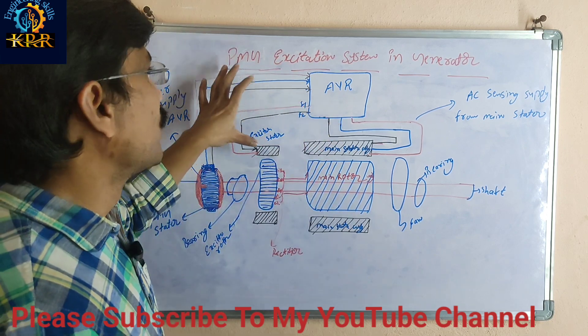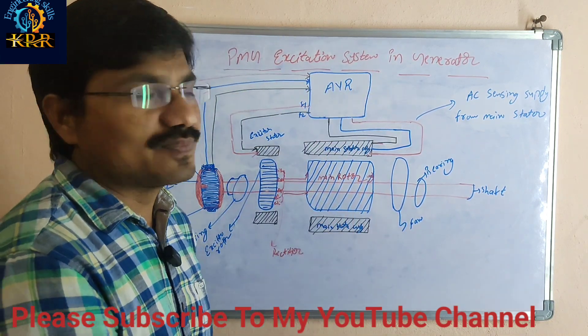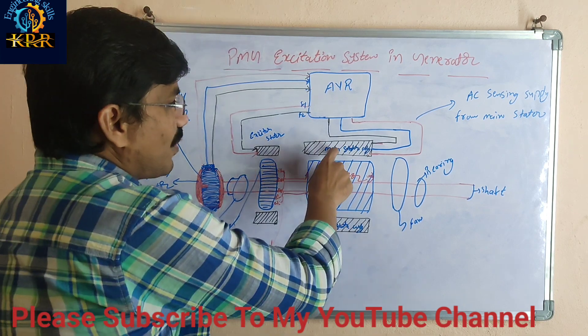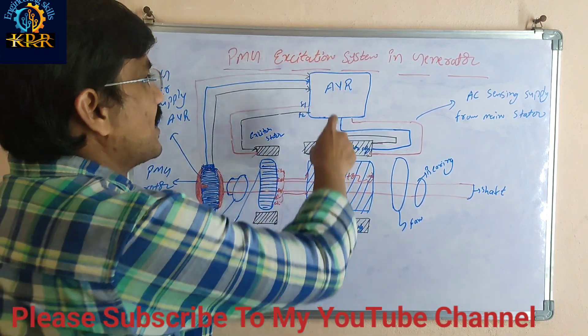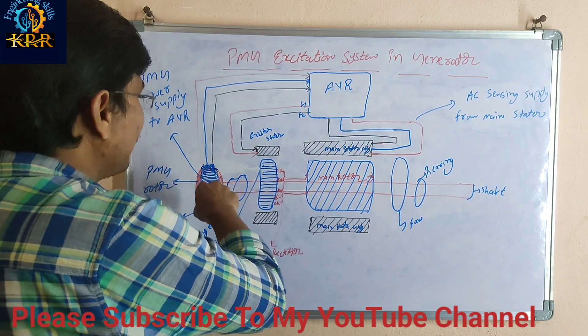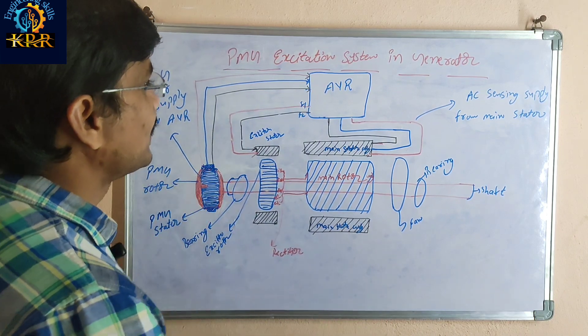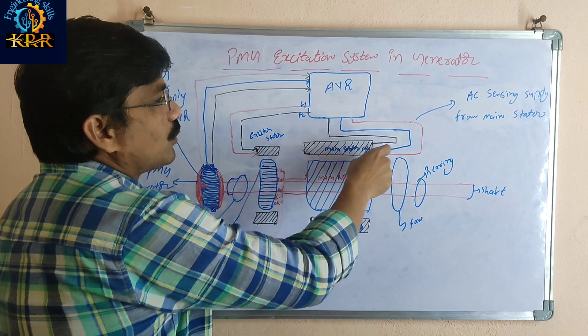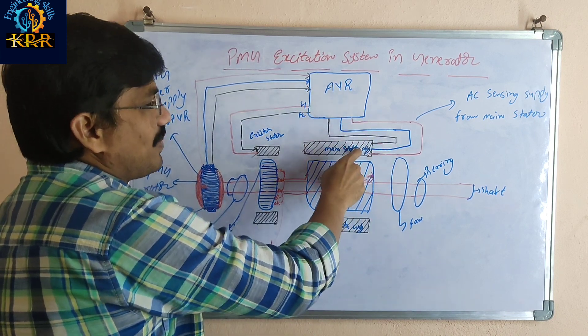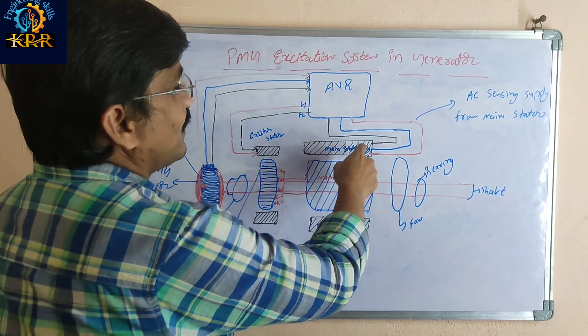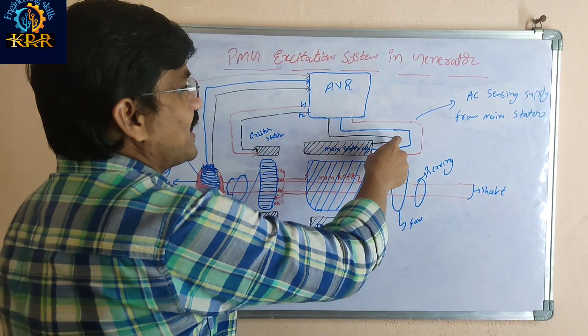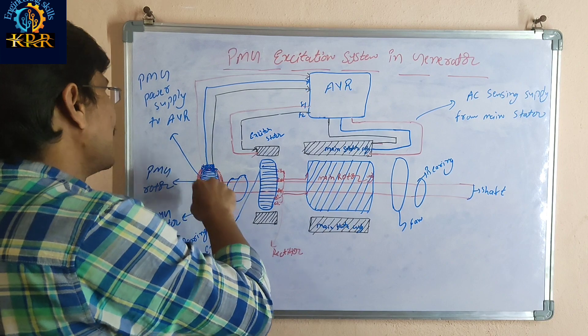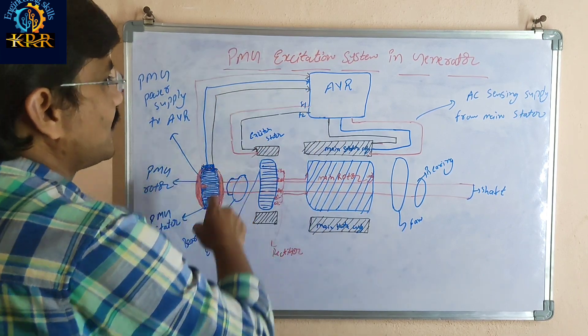That is the default of the self-excitation system, and that's why we use the PMG excitation system. In this PMG excitation system, the power supply is taken from the PMG generator, not from the main stator. The sensing — how much output voltage is coming from the generator — is taken from the main stator for sensing purposes only.